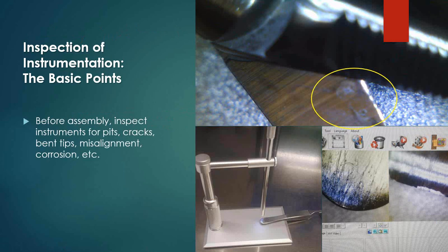Before assembly, you want to inspect the instruments for pits, cracks, bent tips, misalignment, or corrosion. As you can see here on the top right, I took this about a month ago - you can see some corrosion in this scissor. On the bottom left, I used magnification to look at a forceps, and with the naked eye there's no way you could see all those scratches you see on the far right. That's really bad - there's no way I could actually see that. I felt a little something on the forceps, but I didn't know to what extent the damage was.